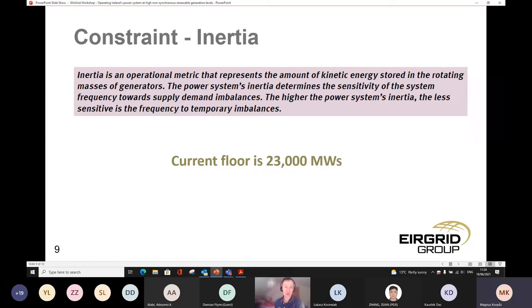Another important constraint on the system is our inertia floor. The current floor for the inertia level on our system is about 23,000 megawatt seconds. This is critical to maintaining the ability of our system to withstand the loss of large infeeds.